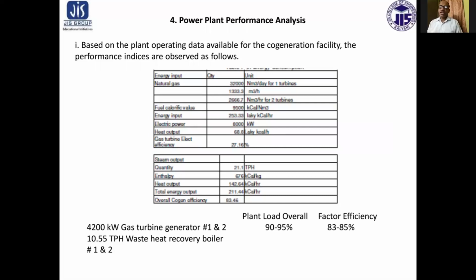Power plant performance analysis. Based on power plant data available for the cogeneration facility, the performance indices are observed. That is, energy input, here as natural gas, quantity 32,000 cubic meters per day for one turbine, that is 1,333.3 cubic meters per hour, and 2,666.7 cubic meters per hour for two turbines. Fuel CV 9500 kilocalorie per cubic meter. Energy input 253.33 lakhs kilocalorie per hour.